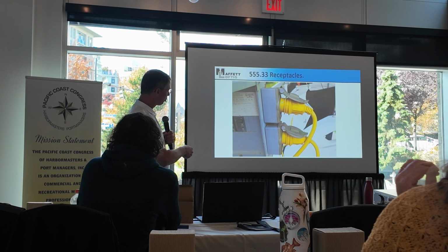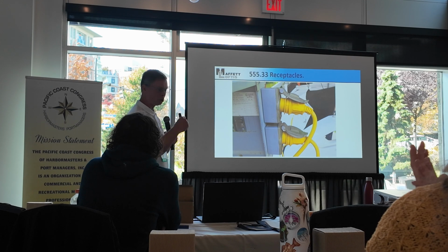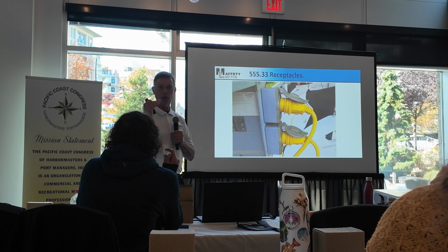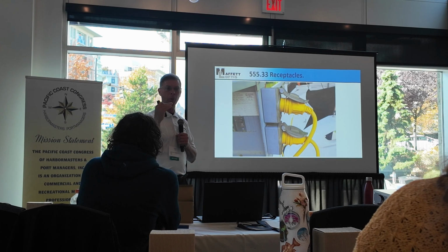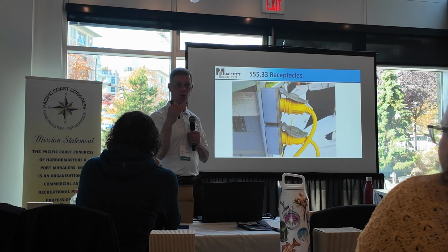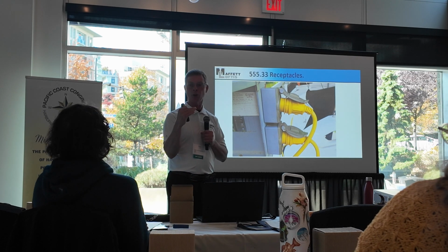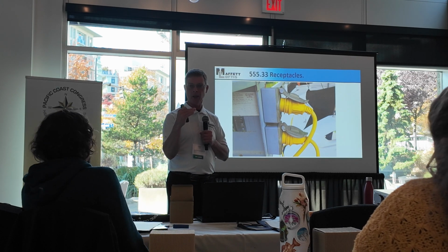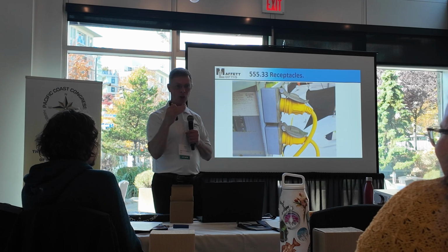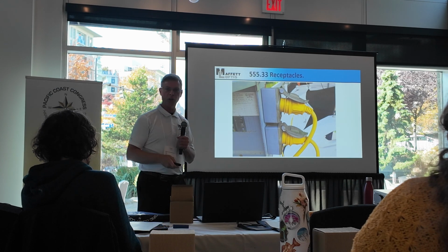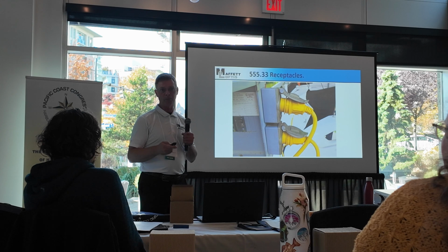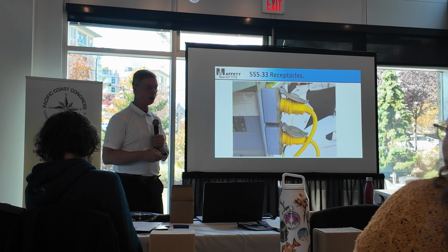What happens to that electrical connection right up here or here when it starts trying to pull out? It's gonna arc. You get a high resistance connection. And high resistance means heat when current goes through it. And guess what heat does? It starts melting plastic down. You got a huge voltage drop, it starts melting plastic down, and it causes heat, it causes a fire. At best, it could cause electric shock at worst.